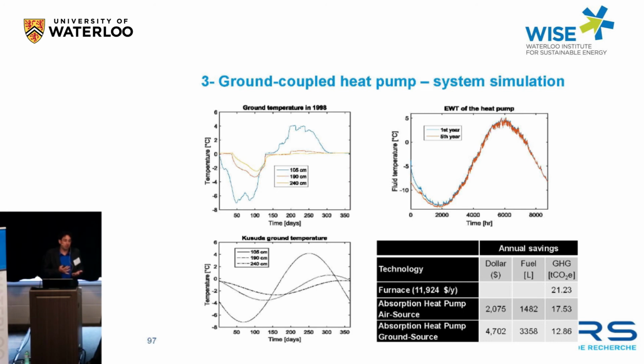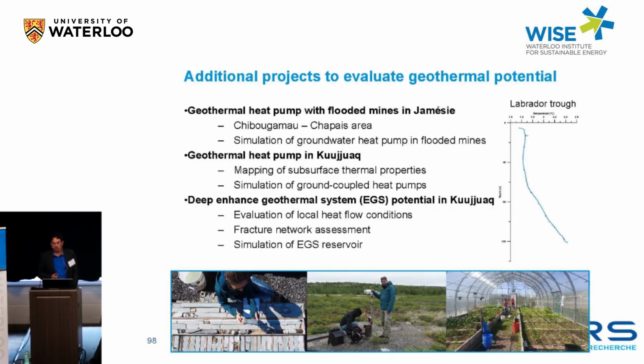And then if you have an absorption heat pump, or just an air source heat pump, which I haven't really discussed but could be an option, and the ground source heat pump, the most interesting option, you can realize energy savings on the order of $4,700 per year, roughly 40% of the energy consumed. So something that could be implemented, I believe, in a short time frame to save on diesel and reduce energy consumption.